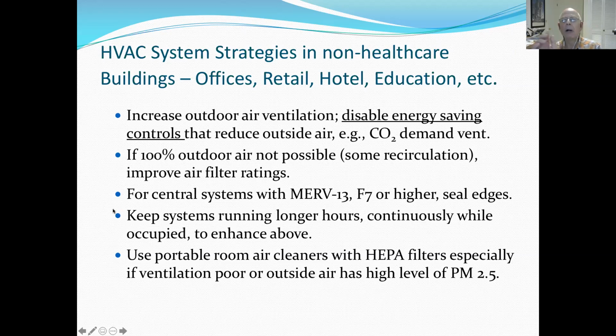Keep them running longer hours. What do we mean by that? Well, I would try to get the system running at least an hour prior to occupancy. And if you're going to have any kind of occupancy past the peak, try to keep it running while people are in the building for the entire time. This is probably going to apply more in the winter season. If it's too cold, you can't run it for an hour in the morning, so at least run it for some time in the afternoon when the outdoor air is a little warmer.